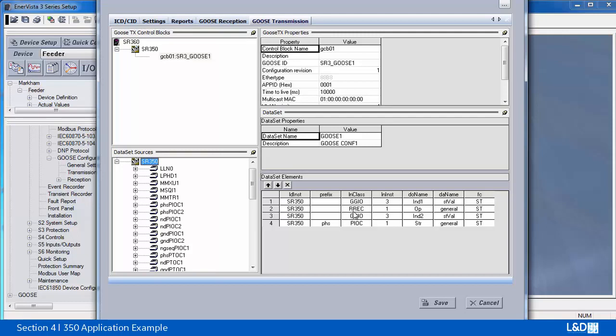Then the second is REC. REC stands for reclose. So the second one is the auto reclose goose message. The third one is GGIO3 again, virtual input 2. This will be used as the manual trip. And the last one is the phase IOC pickup. This will be used to trip the breaker, to reset the breaker status. So we use virtual input 1 to manually close the breaker or REC to automatically close it. Then it will be manually opened by virtual input 2 or automatically opened by the phase IOC pickup. So that's the goose message we're going to publish.